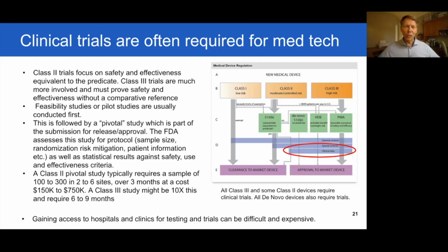For a class 2 device, a pivotal study is a little bit all over the place, but a sample of 100 to 300 is normal, spread over 2 to 6 sites. As a Canadian company, it will usually require that some of those sites be in the US. A typical time is 3 months to data gathering. The companies that I've worked with have spent anywhere from $150,000 to $750,000 on that pivotal study. Class 3 devices, those higher risk ones where you're trying to prove your effectiveness, can easily be 10 times that level of cost and size and require 9 months, a year, even more.